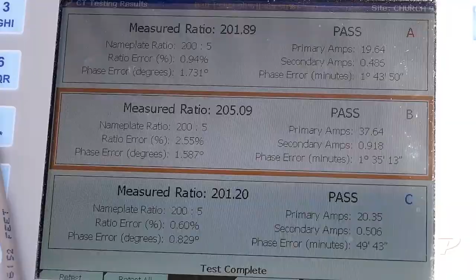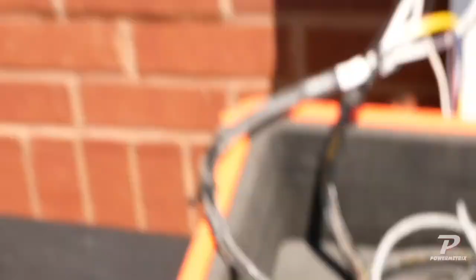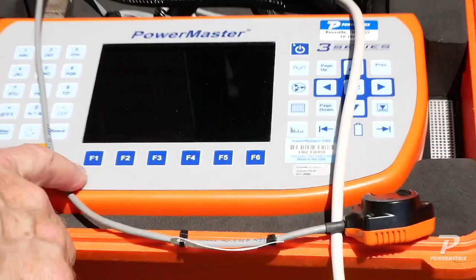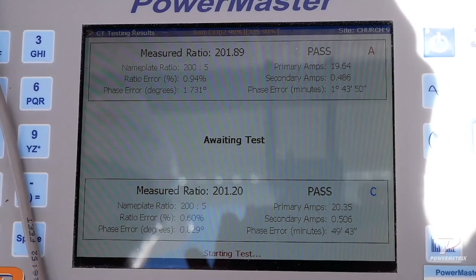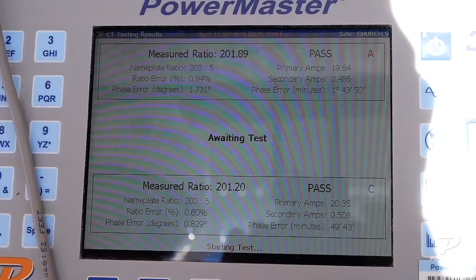So this actually was a much better solution for the utility company. You don't have to change out that CT. It was a corrosion problem. And the folks that work here a lot, their initial reaction was, you know what, let's go down the corrosion path first. So I'm going to hit a retest, and we get a pass again. So you can see that was the problem.